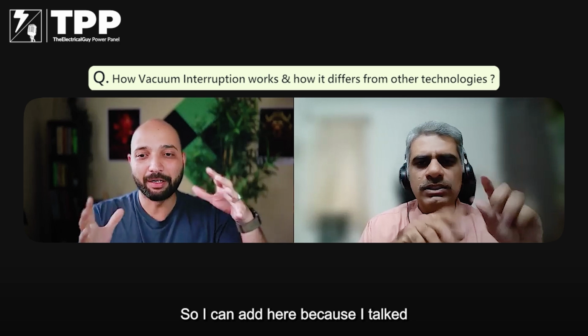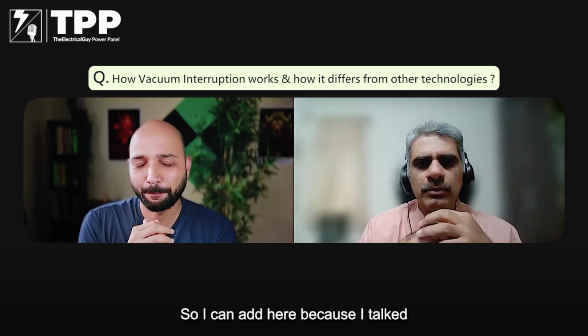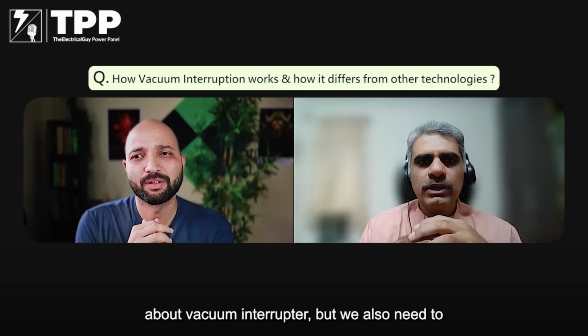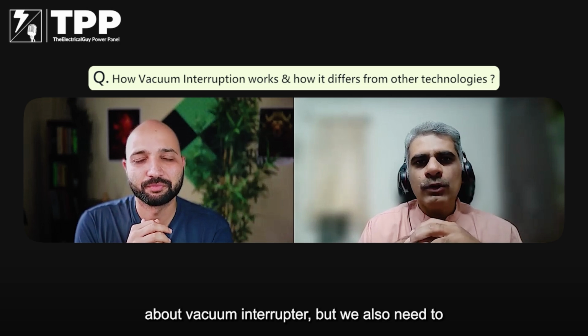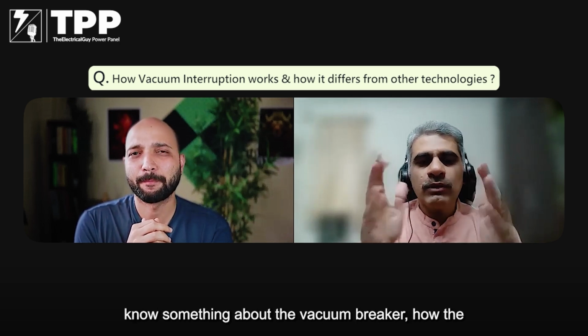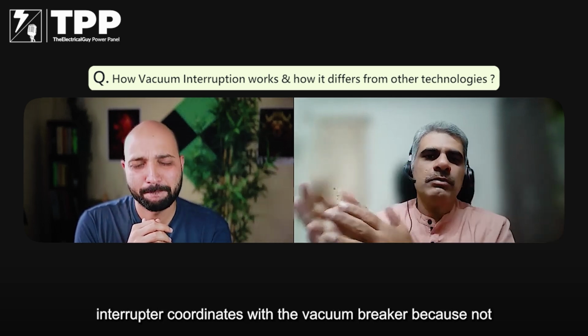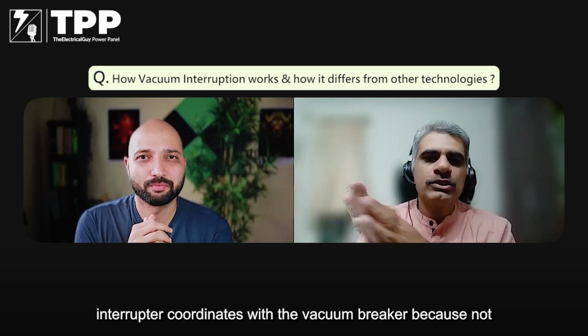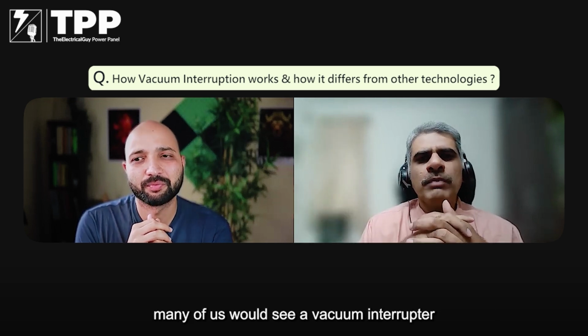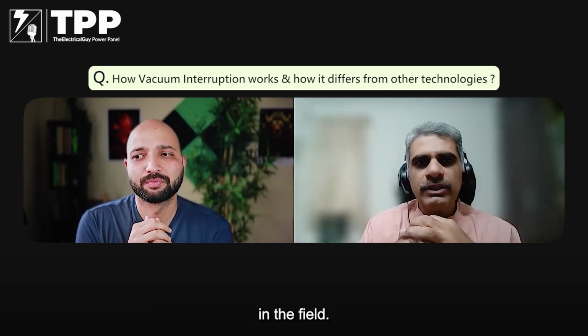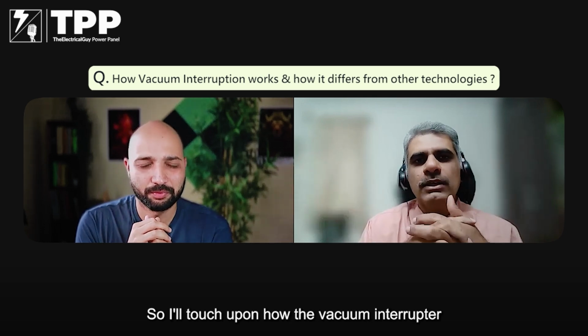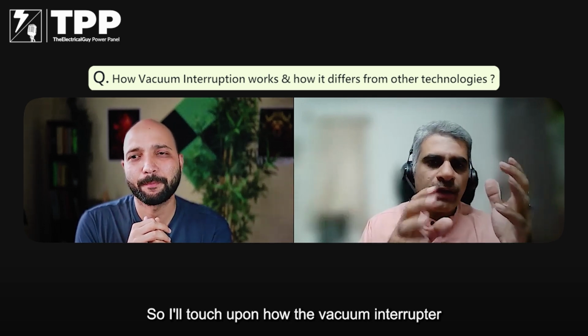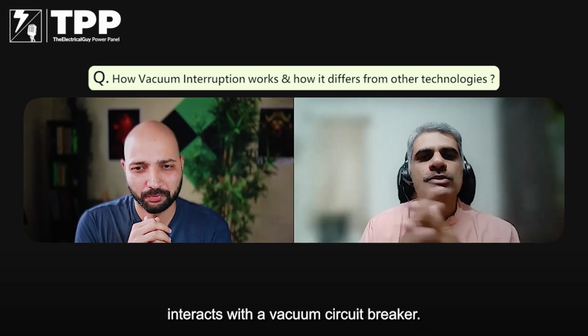Just, if I can add here, because I talked about the vacuum interrupter, but we also need to know something about the vacuum breaker, and how the interrupter coordinates with the vacuum breaker, because not many of us would see a vacuum interrupter in the field. We would see a vacuum breaker, isn't it? So I'll touch upon how the vacuum interrupter interacts with a vacuum circuit breaker.